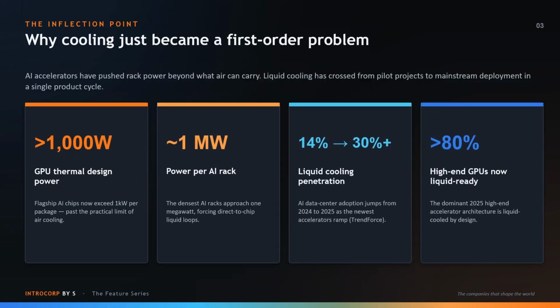Let's start with why cooling suddenly became a first-order problem. For decades, cooling was an afterthought, fans and air handling. That era is over. Look at the numbers: flagship AI chips now exceed 1,000 watts of thermal design power in a single package. That's past the practical limit of what air can carry away. Stack those chips into a rack and you approach 1 megawatt per rack.